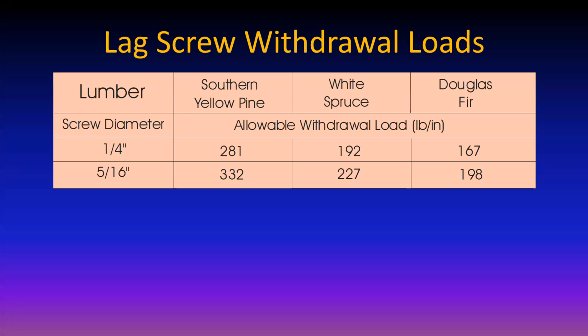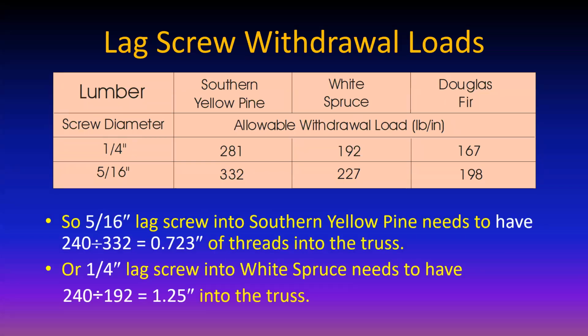Notice I use the word truss and not the plywood decking. The screws have to go down into the trusses to get these ratings here. All right, if you're using Douglas fir, you drop from 332 to 198 pounds per inch. So for the design at hand, what have we got?